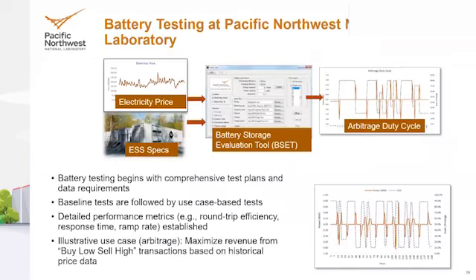Now that you understand the costs and benefits associated with energy storage applications, you have to understand how the battery systems perform. This is essential for capturing the value in real time and characterizing it correctly when simulating performance and designing the systems. So the way we do it at Pacific Northwest National Laboratories, we typically start with the DOE Office of Electricity Energy Storage Testing Protocol, and we run it through a series of tests to establish a baseline from a performance perspective.